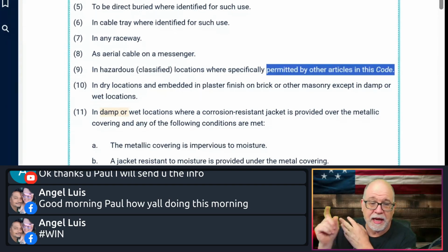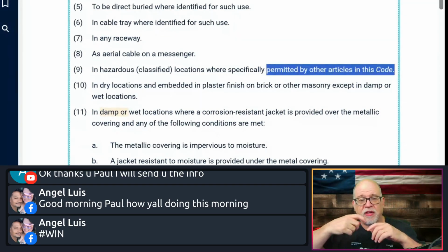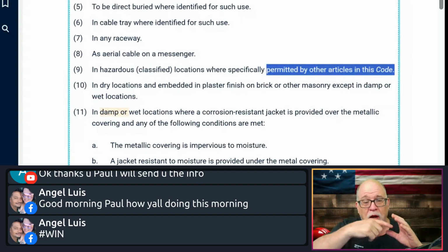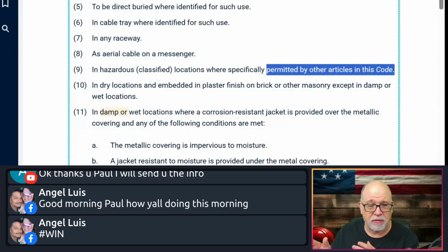For example, it might only allow the continuous corrugated, kind of a welded type. It's not the same as interlocked. Interlocked is just connected by some interlocking metal, whereas the corrugated continuous welded is actually welded, or even the smooth. So you've got to read the specific articles, especially in the hazardous locations, to see what type of MC is allowed. But it's perfectly allowed if that specific article allows the application.